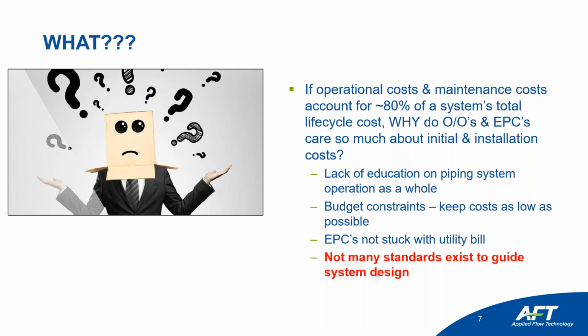Finally, one of the more important reasons is that there are not many standards that exist that will guide piping system design. Okay, there are certainly pipe stress standards, and there are the B31 ASME codes for piping and how to design piping. But the problem is they do not address and provide guidance on the system as a whole. They focus on smaller pieces of it. And so because of that, EPC companies and owner operators are free to choose if they do a flow analysis and calculate system hydraulics or not. And so they have the ability to not even do pipe flow analysis, because why would you do that? Well, you'd have to pay the companies to do it for you.